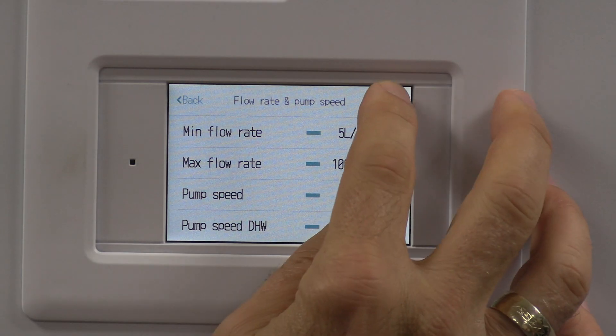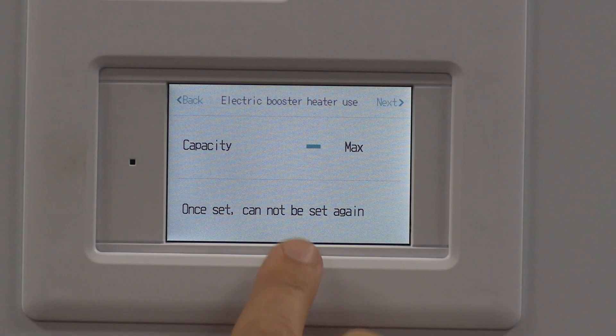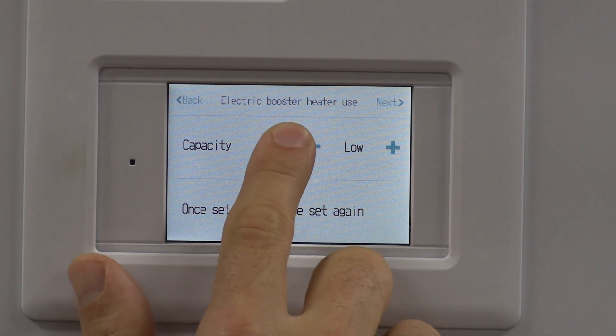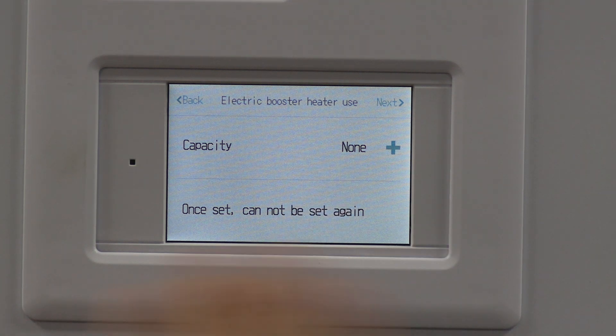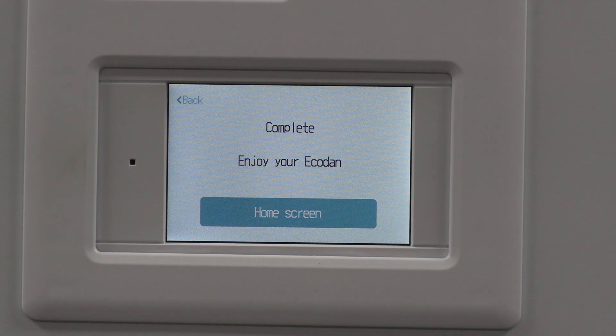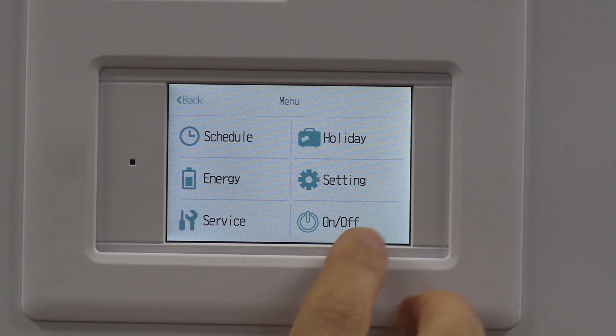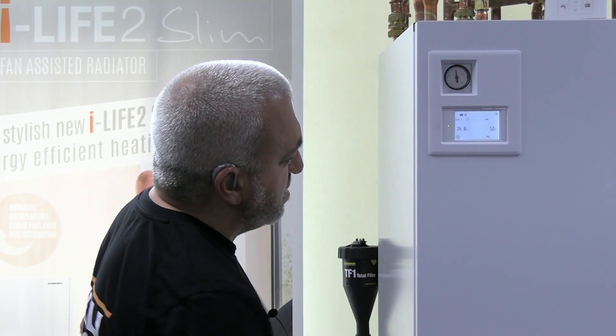Next is the booster heater capacity, which is used on our package cylinders, but we don't actually use it in the UK market - it kicks in at around minus 15 degrees ambient, so it's not relevant here. Setting this up in the UK, I'll turn it all the way down to none - non-active. Then it says thank you, you're complete - the unit is commissioned and ready to go. Click simple, turn it on, and it goes straight to the pre-configured settings, operating in both heating and hot water.